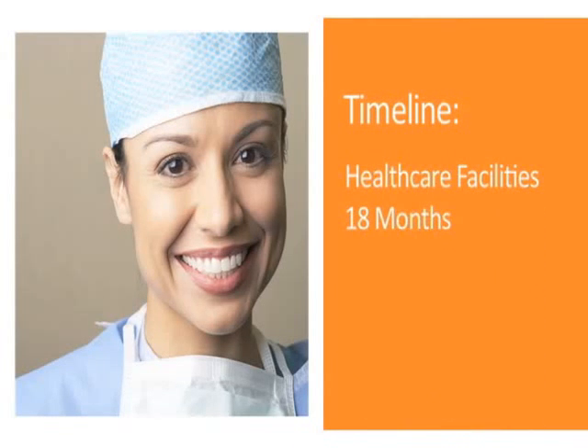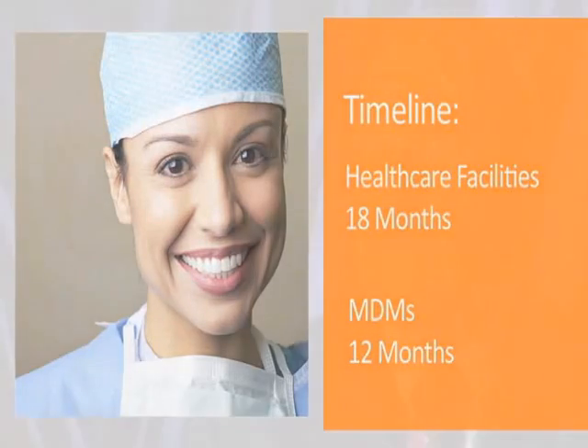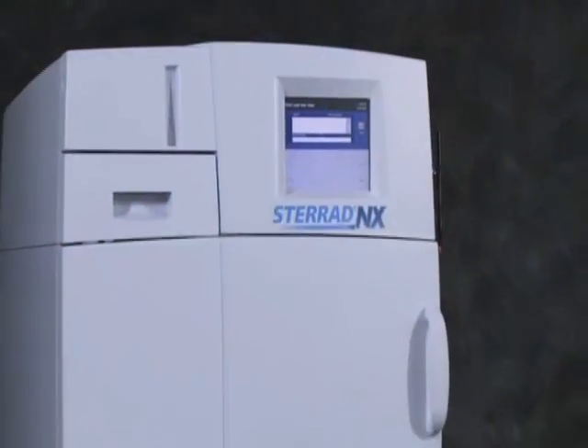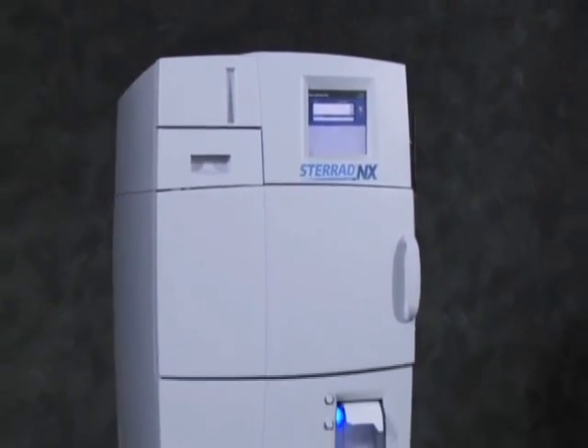Alternately, the medical device companies, or MDMs, have a different timeline. The FDA gave the hospitals 18 months to make the transition, but they gave the medical device companies only 12 months. So within that 12 months, the FDA expects that each medical device manufacturer who has Steris System 1 within their instructions will have it removed and will change in its place to something that we'll call a legally marketed device.